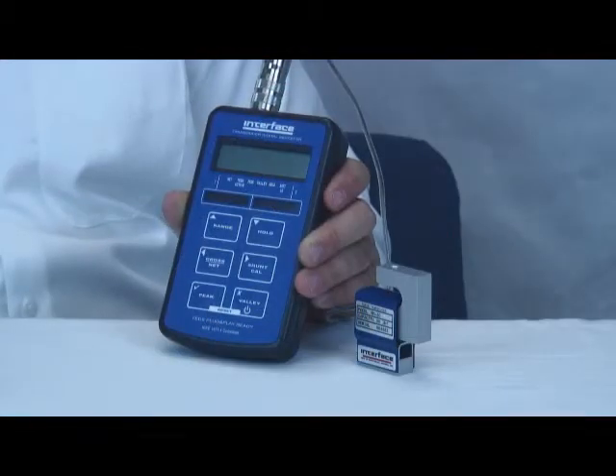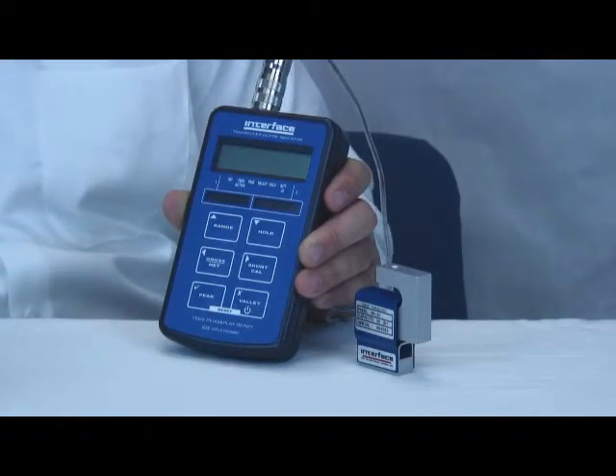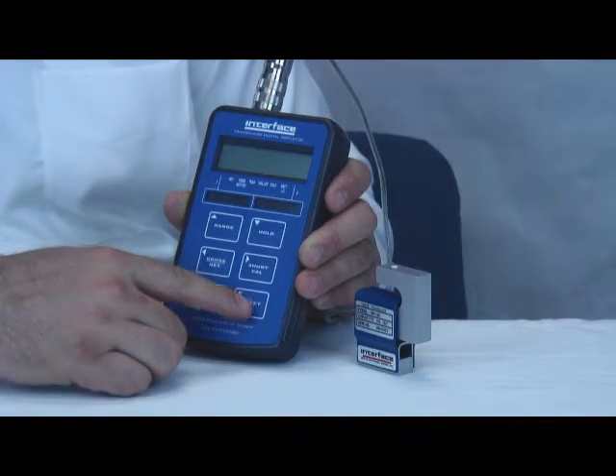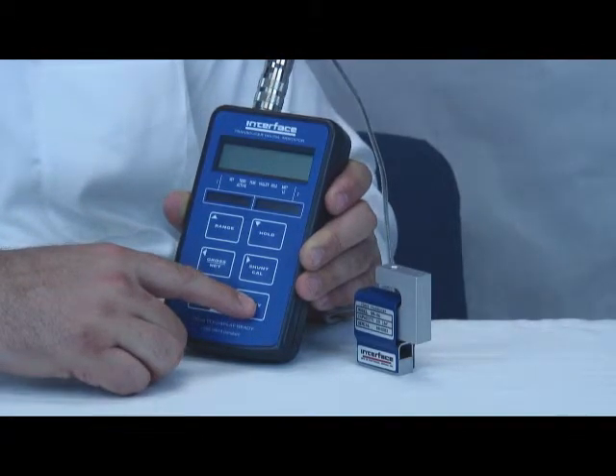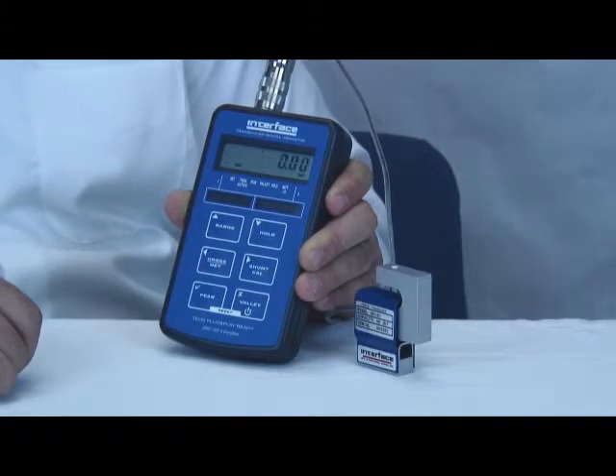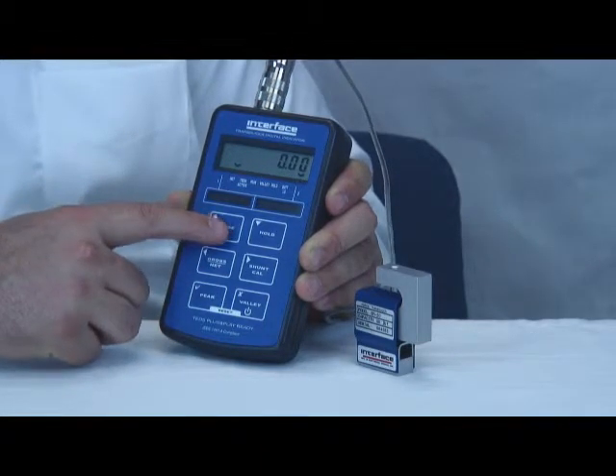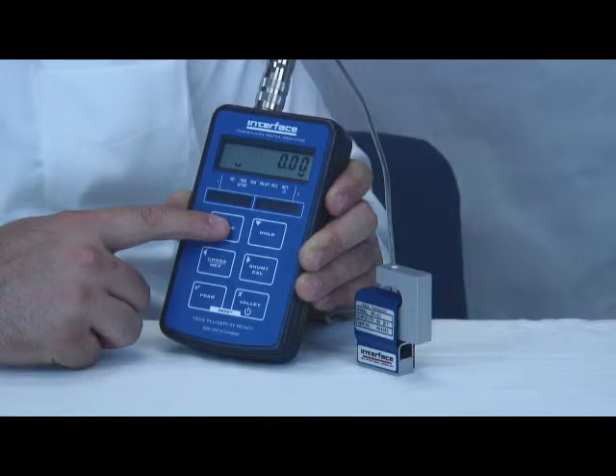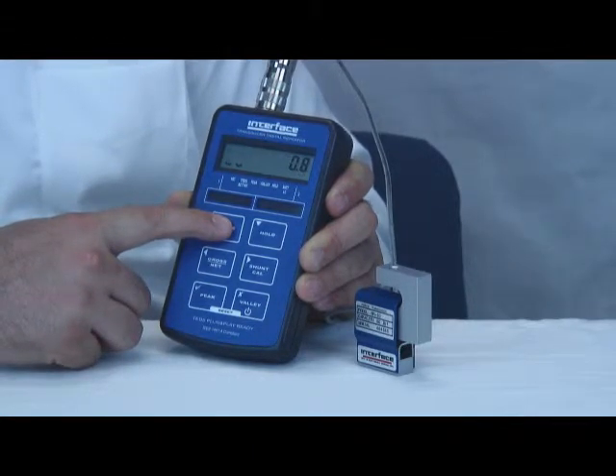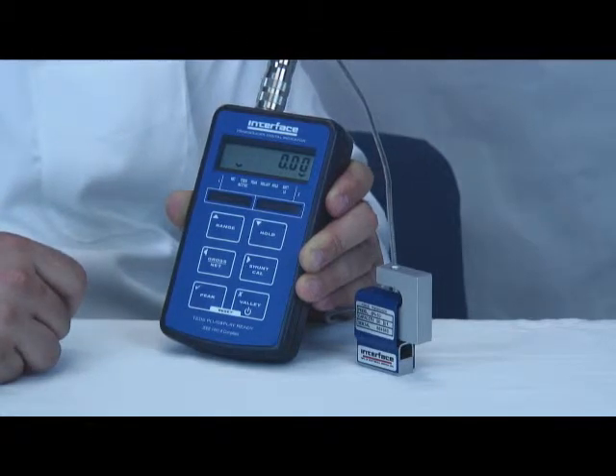I'd like to briefly explain the functions of the buttons on the 9320. First off, the power button. Pressing and holding this button turns on and off the power. Starting at the top, there's a range button. This basically allows you to use two different ranges with the 9320. Pressing the button changes the range. You can calibrate two different ranges, and that second range can be used for either a second load cell or for different units of kilograms.